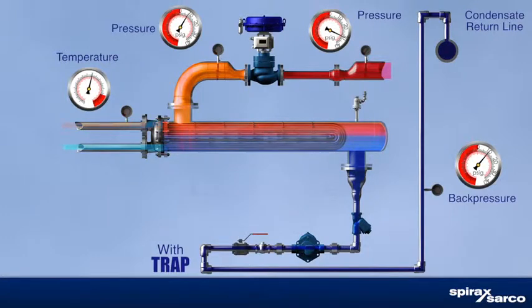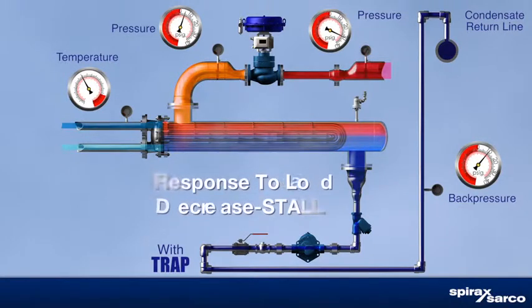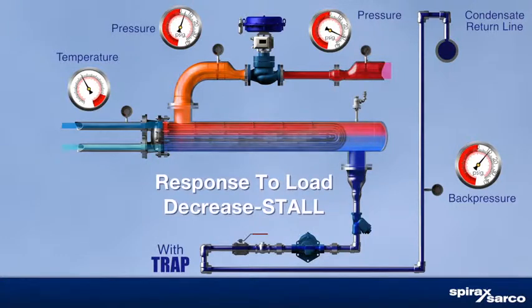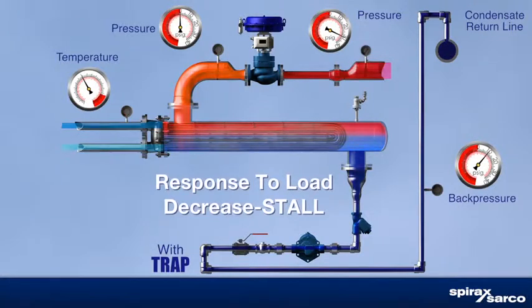This happens in all heat exchangers, whether properly sized or oversized. This causes condensate to flood the steam space, known as heat exchanger stall. In other words, the pressure in the heat exchanger is equal to, or less than, the total back pressure imposed on the steam trap, sometimes even attaining vacuum.